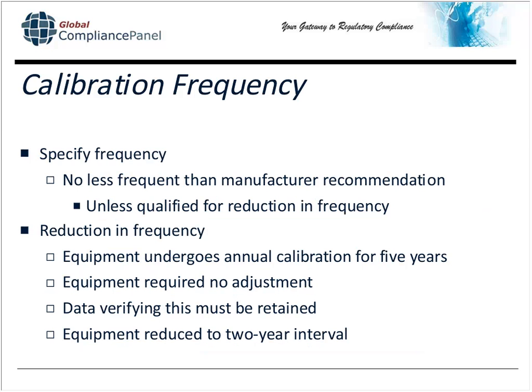You're going to specify the frequency of how often your equipment is calibrated. Definitely don't make it less frequent than the manufacturer recommendation unless you've been qualified. As I mentioned earlier with the example of no adjustment required over 5 years, we're going to go ahead and decrease that in frequency from every year to every other year. And of course you must have data verifying this, not just that it hasn't been adjusted for 5 years. What many firms choose to do, that I'm actually a big fan of, is that as part of this justification they have an engineer sign that based on the use of this piece of equipment and its history, it's okay to reduce the frequency to every other year.